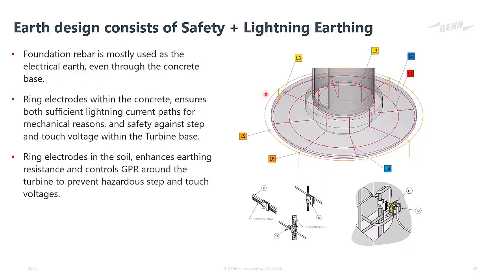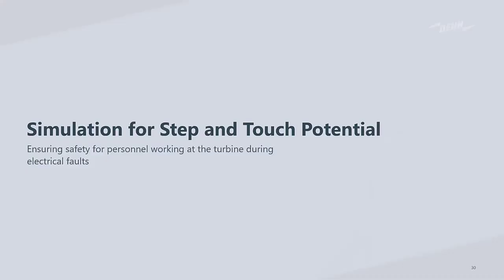But again, the rings are mainly there to control ground potential rise and thus avoid hazardous step and touch voltages in and around the turbine base. Now, just a simple simulation for step and touch. This was done using XGS Lab. This is just to show you typically what it would look like, but it's still very similar to doing a normal earthing design for something like a substation. It's just required that you can simulate both above ground and underground structures, or within and outside concrete, add all those conductors and things like that as well.